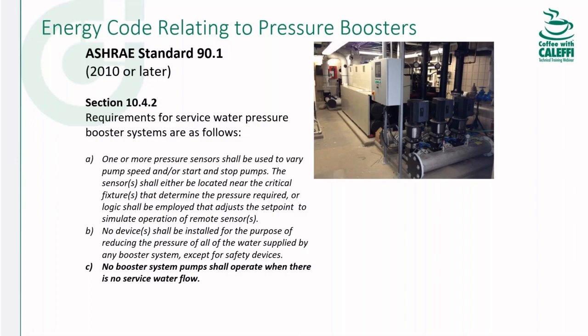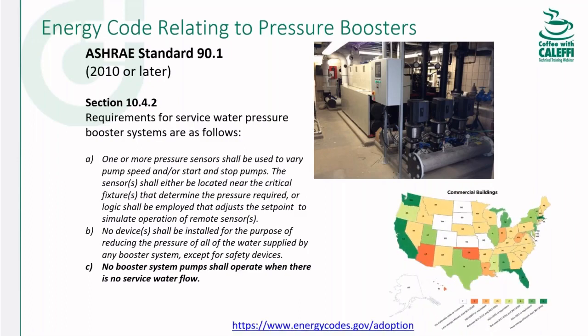And the most important one for me here is that no system pumps shall operate when there's no service water flow. In other words, when nobody's using water in this building, stop your pumps. That's the biggest energy saving thing you can do with a plumbing system today. And if you want more on this, go to energycodes.gov and then /adoption. That'll tell you which states are in what version of the code each state is following. Yeah. Thanks, Reece.